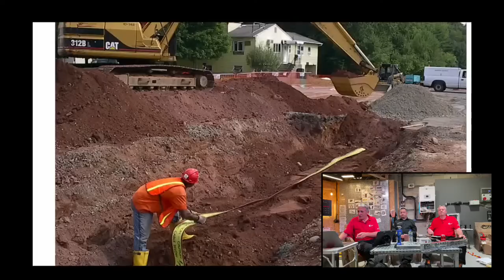But then there's an addition - a new column, which refers specifically to armoured cables buried directly in the soil. You'd have thought that was already in there, but it wasn't - it was cables in a duct within the soil. The ratings were based on ducted cables, whereas if you look in the IEC standard, you can get more current out of a cable that's buried direct.